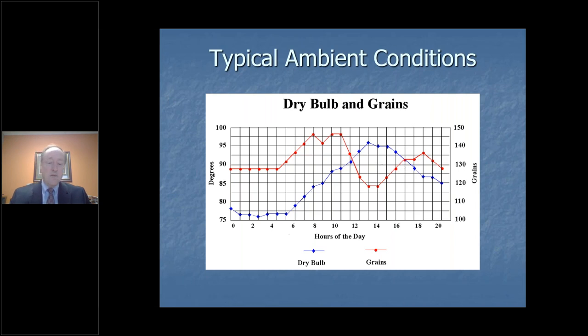So the problem is, if we designed all of our air conditioning systems for our building, whether it be a hospital or a school or an office building, for that 2 to 3 o'clock in the afternoon condition, then we may very well have missed the peak moisture level over here. Think of this as a school. If you open up all the dampers to bring in all of your ventilation air in the mornings because your students and your teachers are starting to come in, you may have opened up dampers at 7 o'clock in the morning and it was fairly mild outside temperature wise, your sensible load, but your moisture level was very high. And if all you had on the walls of your classrooms was a thermostat, it's not reading very much of an increase in temperature, but yet you have packed your building full of moisture and you might have a humidity problem in that building. So it's this particular information that encouraged ASHRAE to look at the tables.